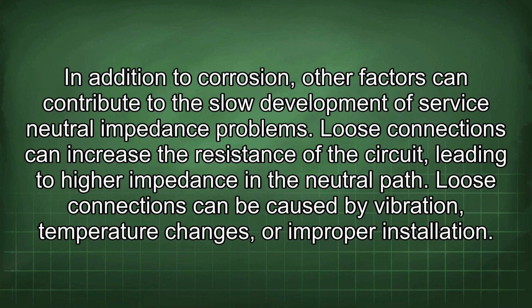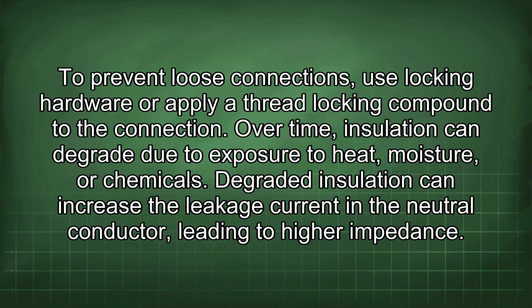In addition to corrosion, other factors can contribute to the slow development of service-neutral impedance problems. Loose connections can increase the resistance of the circuit, leading to higher impedance in the neutral path. Loose connections can be caused by vibration, temperature changes, or improper installation. To prevent loose connections, use locking hardware or apply a thread locking compound to the connection.